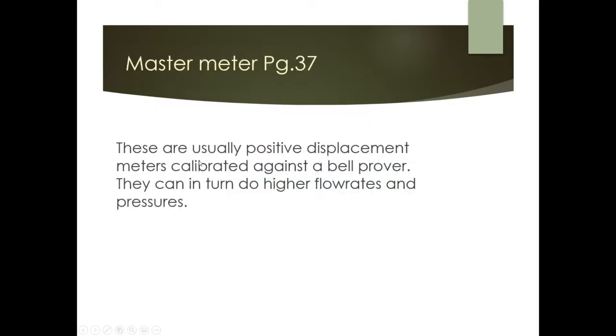Gas master meters are usually positive displacement or turbine meters, calibrated against a bell prover. Once calibrated against the bell prover, they can in turn be used for higher flow rates and pressures that the bell prover itself cannot handle.